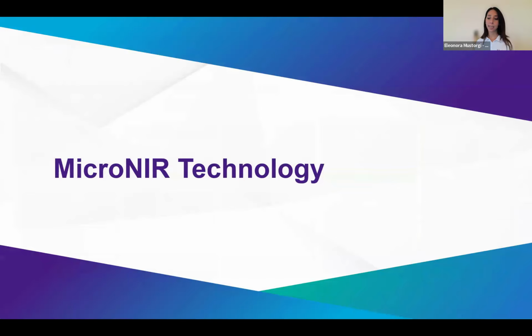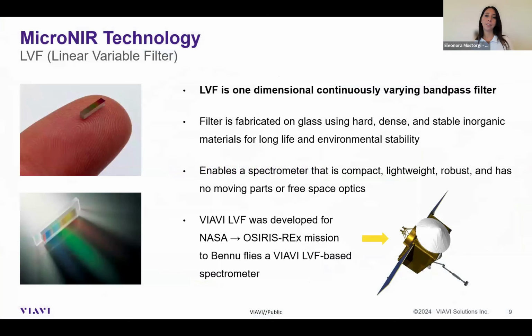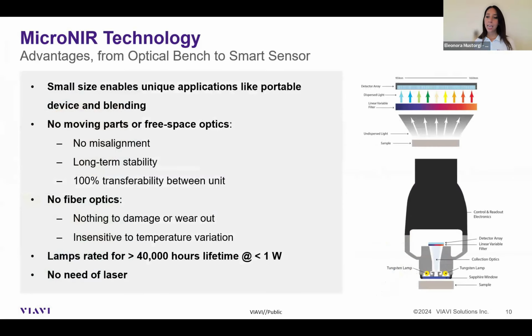A couple of words about the MicroNIR technology. The core of our devices is the linear variable filter. The LVF is a special bandpass filter with a wedge shape, which allows the light to be dispersed according to the position. As you can see in the picture, the small dimension of the LVF allows us to obtain very compact and robust devices without moving parts inside. In this slide, you can see the cross-section of our optics. The linear variable filter is mounted directly on an InGaAs detector in which each pixel detects a single wavelength coming from the light transmitted by the sample.